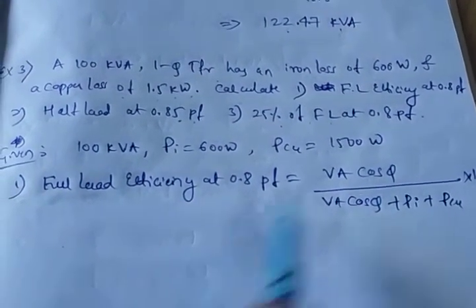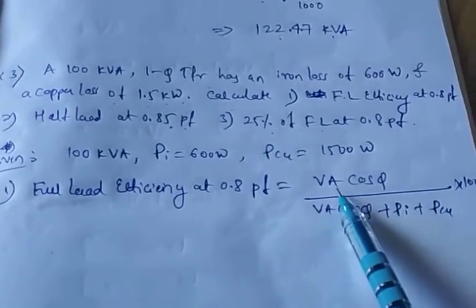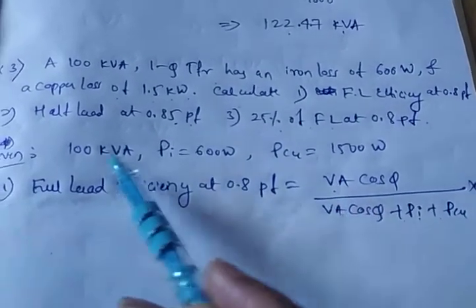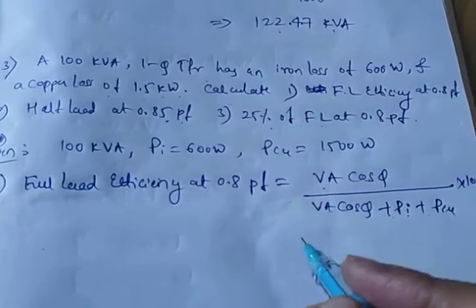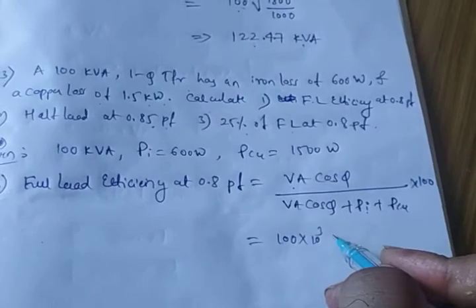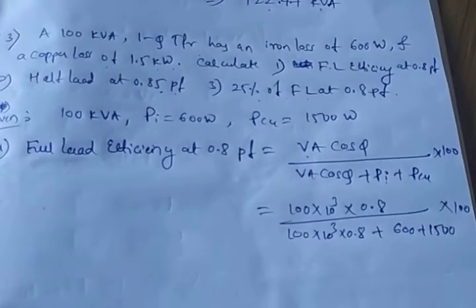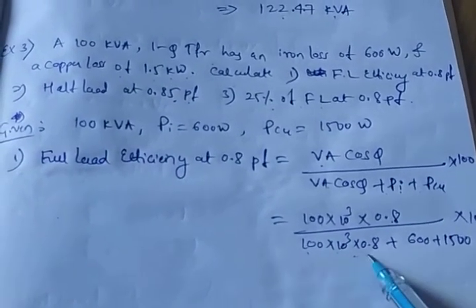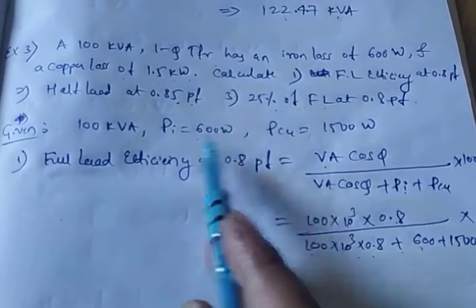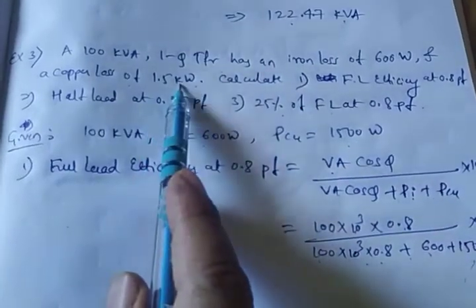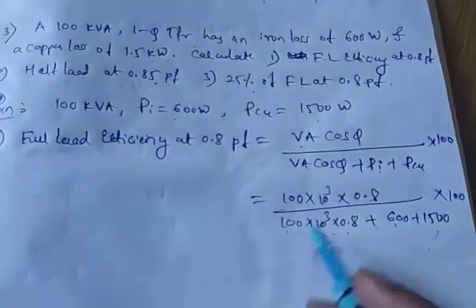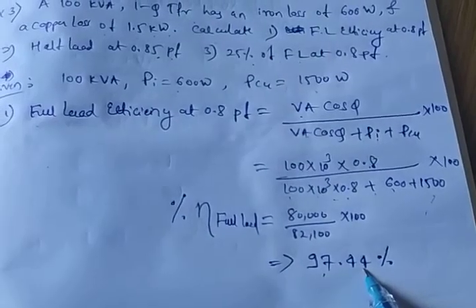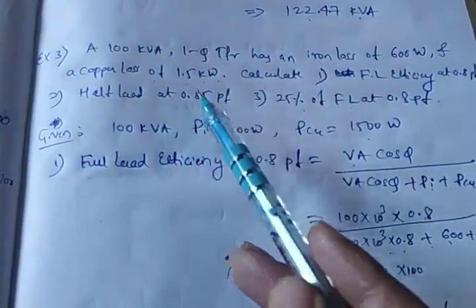The first part is full load efficiency at 0.8 power factor. The formula is: VA × cos φ divided by (VA × cos φ + Pi + Pcu) × 100. VA is 100 kVA, so substituting: 100×10³ × 0.8 divided by (100×10³ × 0.8 + Pi = 600 watts + Pcu = 1500 watts) × 100. The efficiency at full load is 97.44 percent.